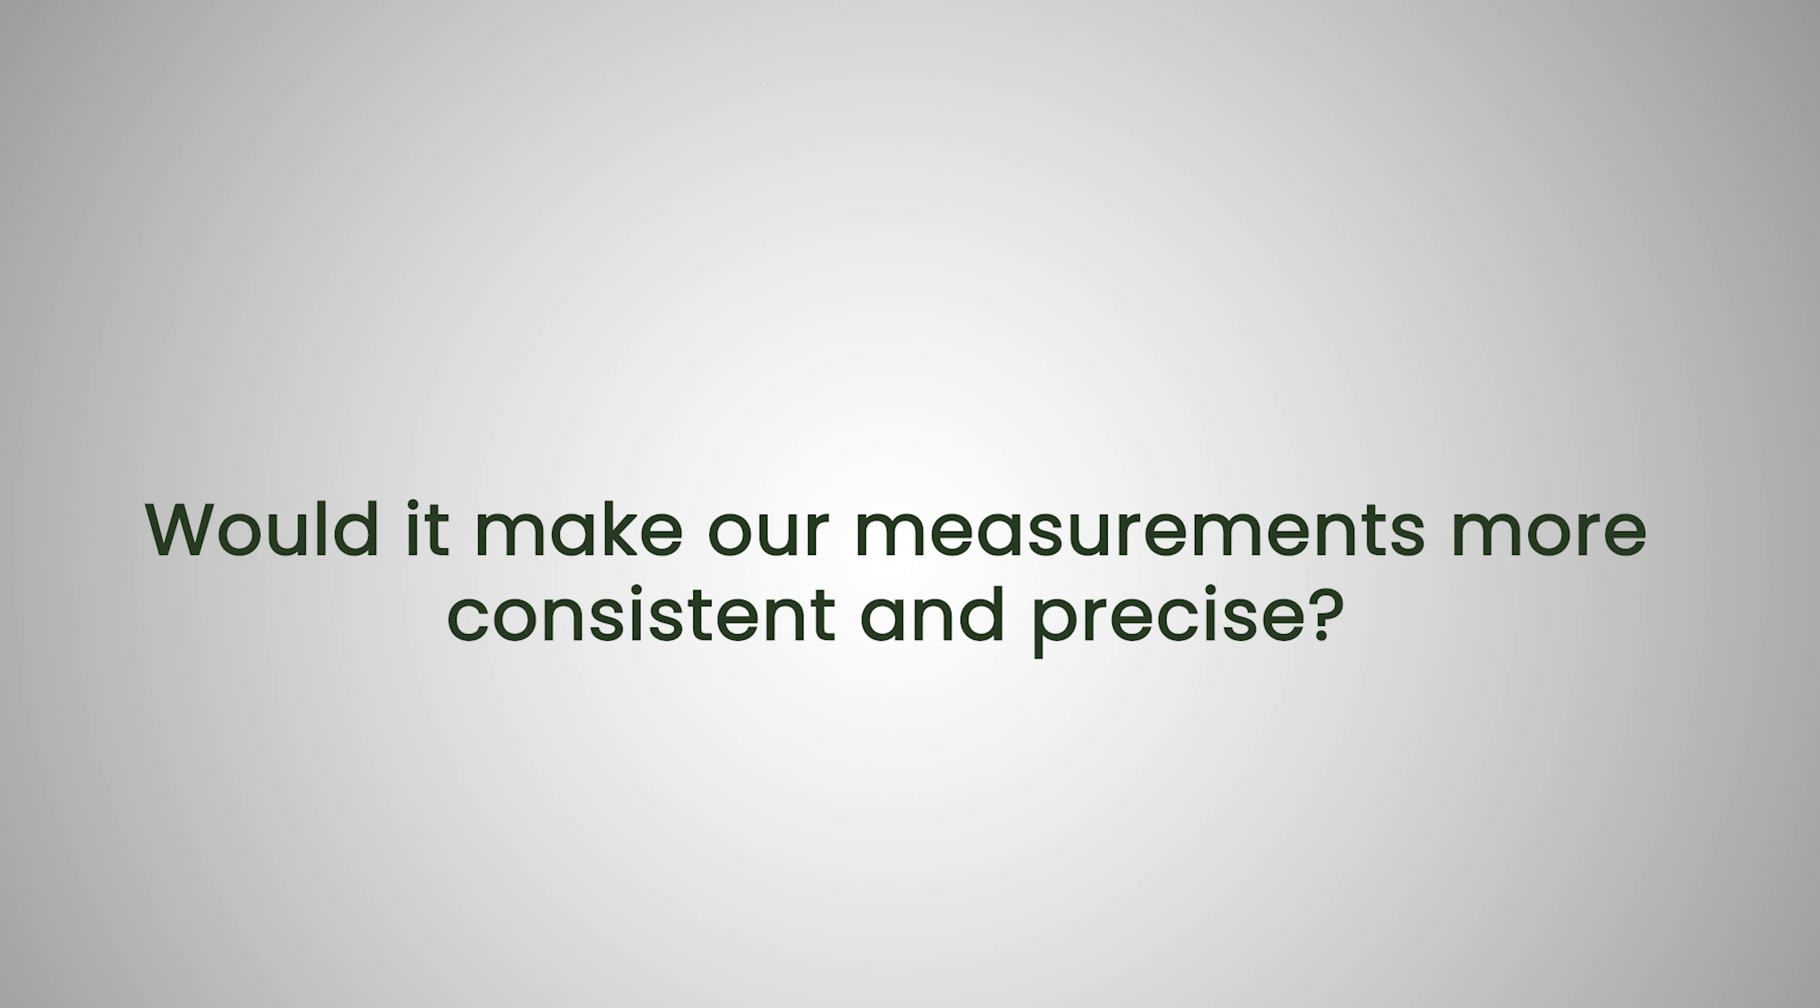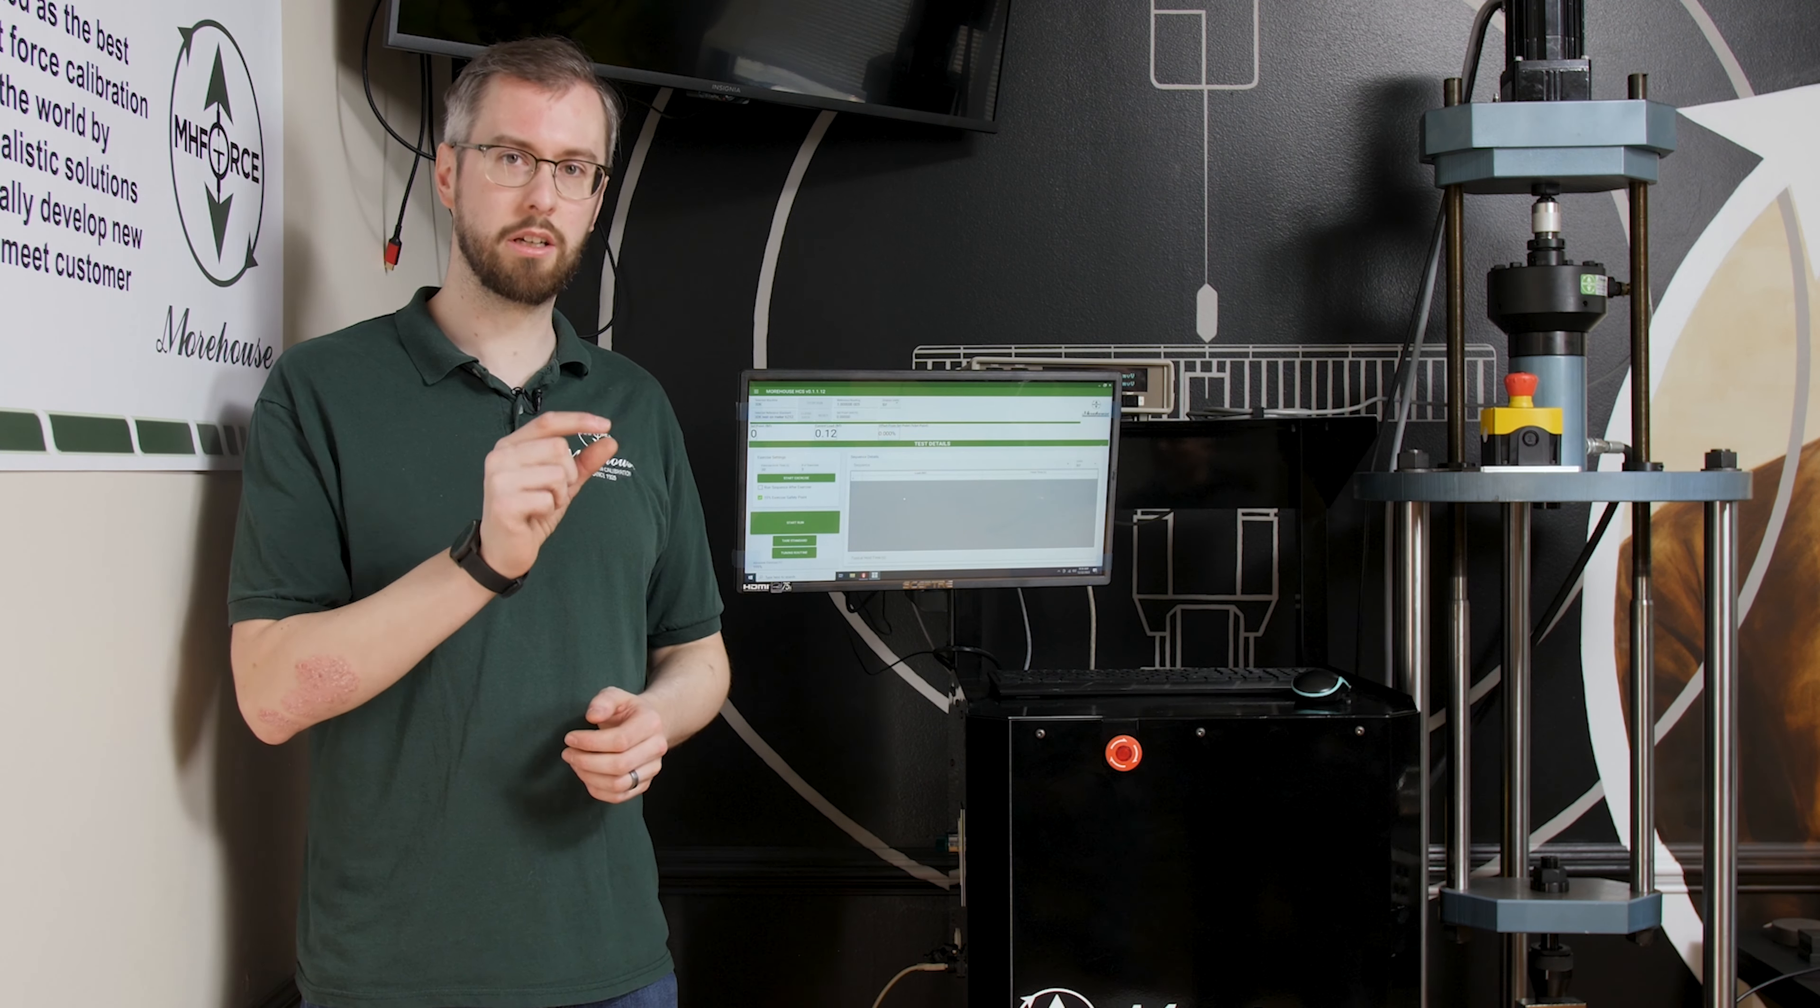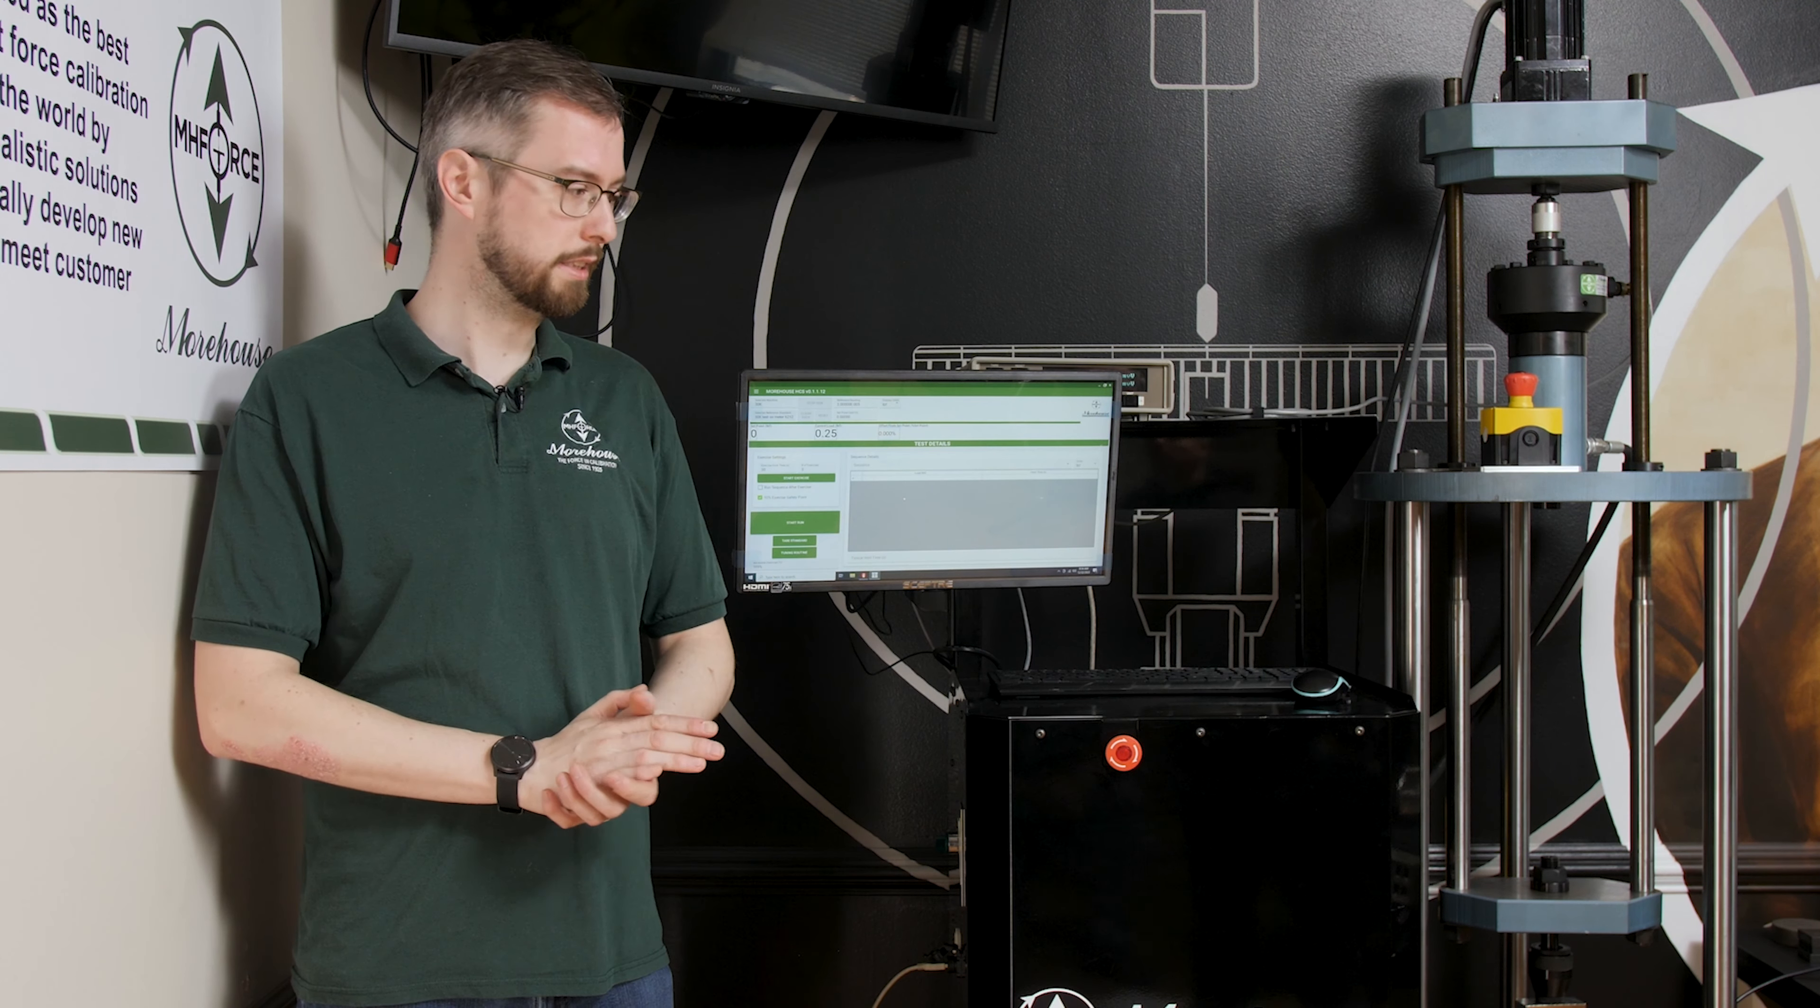Would it make our measurements more consistent and precise? Yes, so like I mentioned, the automated system can hold a load better than a human can generally do. So you can configure how close you want it to hold the load when it takes a point. By default, that's 0.002% of full scale, but that can be dialed in even tighter if you want to, and then you can also set how long you want it to hold that load before it takes a reading. So if you want to hold it for 30 seconds or 45 seconds, you can set that in the software.